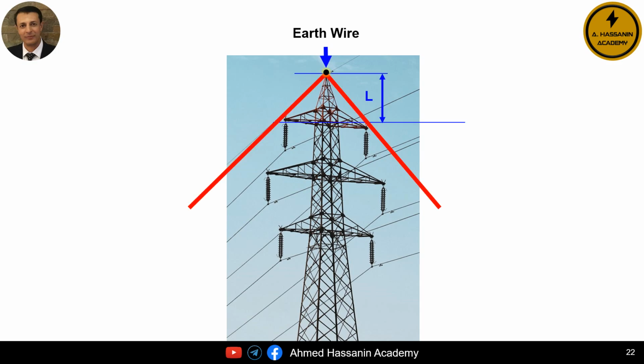Let us assume, for example, that the protection angle for this overhead tower is 30 degrees. This means 30 degrees to the right and 30 degrees to the left. It is important to know that to achieve this 30-degree protection angle, the earth wire, also called the shield wire or ground wire, must be installed at a certain height, as clearly shown in the image before us.